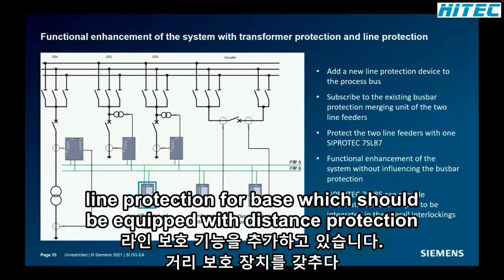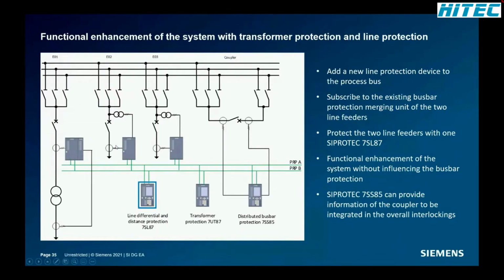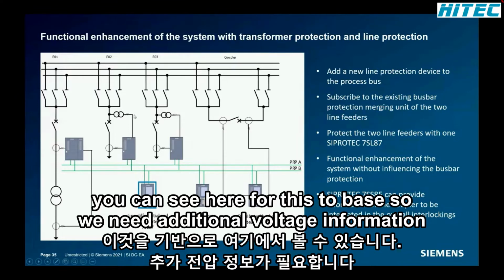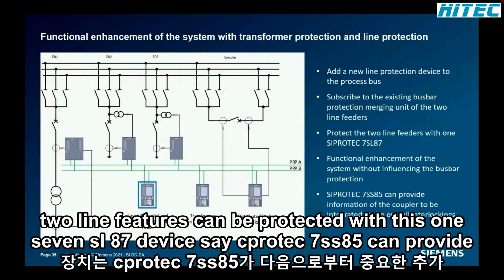Next step in our virtual road to a digital substation is adding a line protection. For bays which should be equipped with distance protection, the voltage information must be collected additionally. You can see here for these two bays, we need additionally the voltage information. Of course, we need a line differential and distance protection device, e.g. a 7SL87, which has to be connected to the redundant Ethernet LAN. Two line feeders can be protected with this one 7SL87 device. The SIPROTEC 7SS85 can provide additional important binary information from the coupler for substation-wide interlockings.